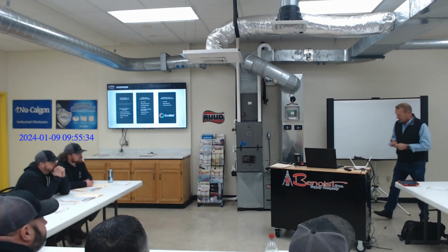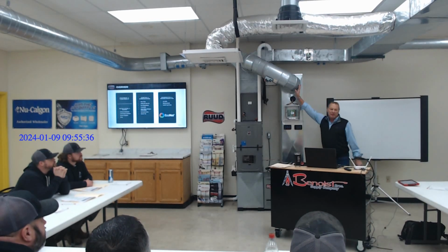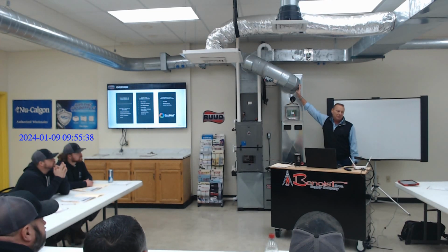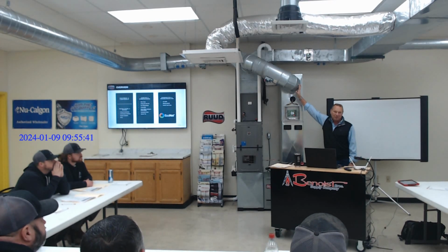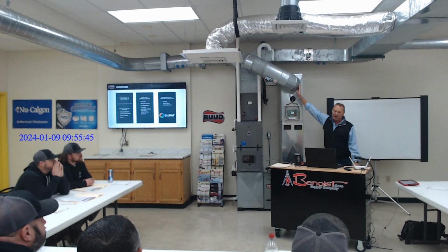How many people understand how these motors work? I'm going to start this boring, but what we need to understand to begin with is that we know how these motors work, because where I'm starting with this is CFM and static pressure. The old days of zoning with a straight zone system, we put a bypass right in a return drop right off of the plenum, and a barometric damper. You still can do that. This was never really a great way of doing it.